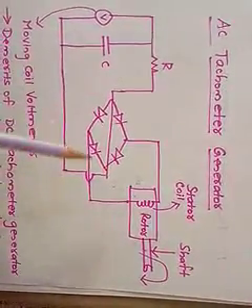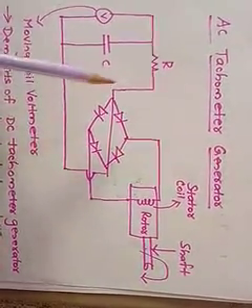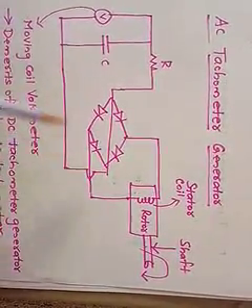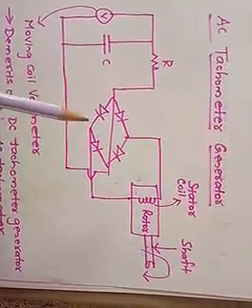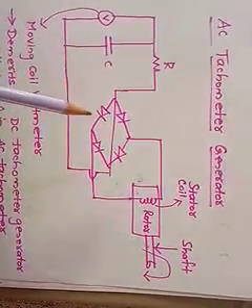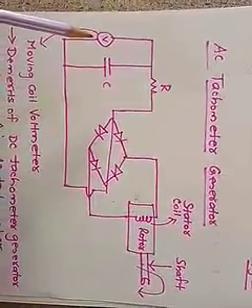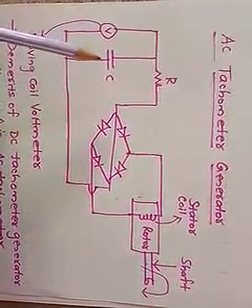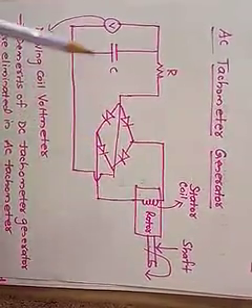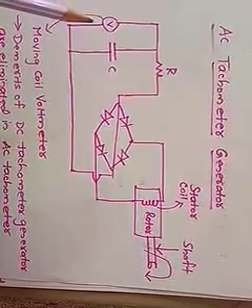This EMF is rectified by a bridge rectifier arrangement, which converts the AC voltage to DC voltage. This DC voltage is measured using the output voltmeter V. The capacitor is meant to remove unwanted ripple present in the output voltage. This is how the AC tachometer generator measures the output voltage, which is calibrated to indirectly measure the speed of the shaft.